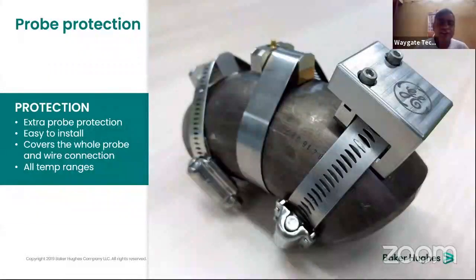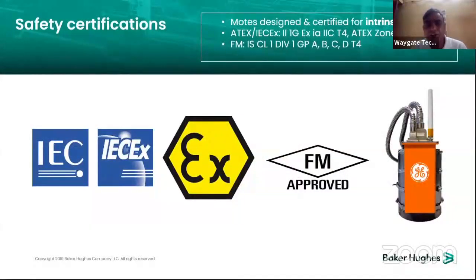Probe protection is easy to install. The probe is the heart of the system, providing the complete signal and data. It is completely mounted with protection for temperatures, the whole probe, and wire connections. For large diameters — over 50, 60, or 70 inches — there is a special system designed with probes that can handle 24 to 72 inch diameter and temperatures from minus 40 to 400 degrees Celsius, with a double strap for complete protection. The motes designed is certified for intrinsic safety, all ATEX zone certified, and meets all global classification standards.